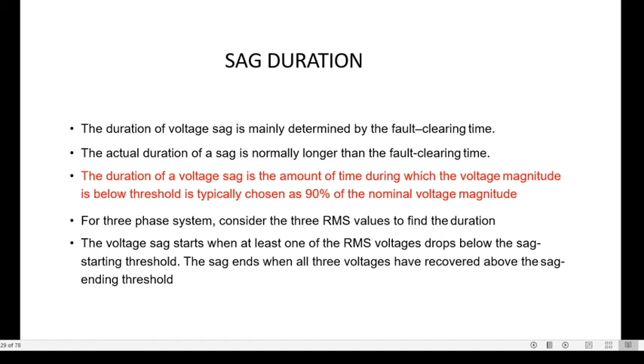The duration of the voltage sag is mainly determined by the fault clearing time. The actual duration of the sag is normally longer than the fault clearing time. The duration of the voltage sag is the amount of time during which the voltage magnitude is below the threshold, typically chosen as 90% of the nominal voltage magnitude, and that decides the type of the sag: instantaneous, momentary and temporary. For the three-phase system, consider the three RMS values to find the duration. The voltage sag starts when at least one of the RMS voltages drops below the sag starting threshold. The sag ends when all three voltages have recovered above the sag ending threshold. So that will define a symmetrical sag and unsymmetrical sag.